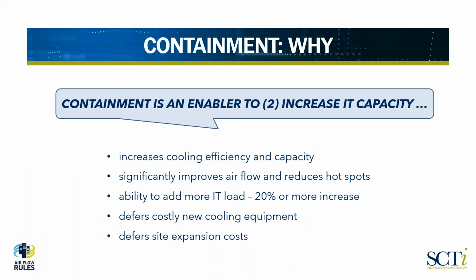The other aspect on why is the fact that containment is an enabler to increase IT capacity. As you improve the cooling efficiency, you actually improve the capacity for that system to accommodate more IT equipment. The result is significant improvement in airflows and reduction in hotspots. We've seen quite substantial increases. There was a study done a couple of years ago on containment, and they referenced a 20% increase in IT load by doing containment. You'll see in our case studies that our results are substantially higher than that. I think 20% is very much a baseline.